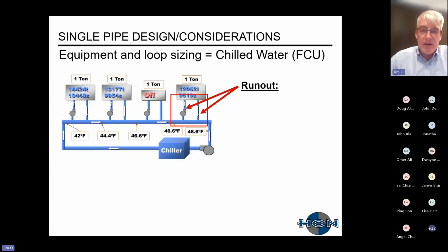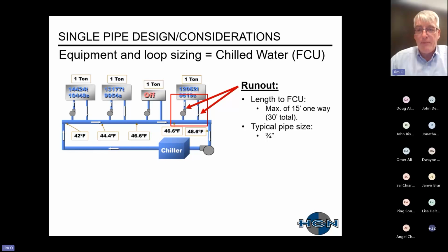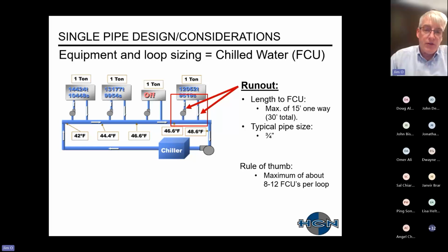What you're looking at now is your runout piping. This is the length going to the fan coil. You want to have a maximum of about 15 feet one way, 30 feet in total. And then a typical pipe size is 3/4 of an inch, either half inch or 3/4 inch. And then a rule of thumb for the number of fan coils on each of the loops is about 8 to 12. Once again, you're concerned about the last fan coil and the return water temperature.